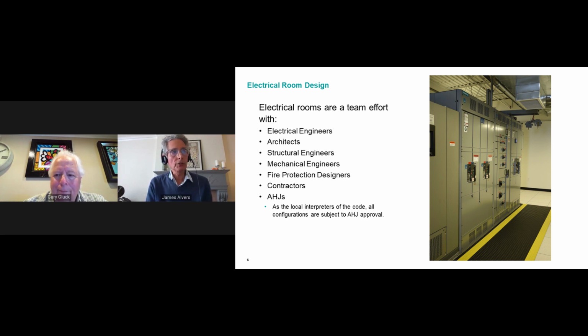The picture you see in the slide shows a switchboard, and we're going to be talking about switchboards, not switchgear. So typically you can place them against the wall. There are exceptions on occasion. You see in this case some individually mounted insulated case breakers, and another section with some molded case group mounted breakers. Both are okay for generator switchboards. Obviously, you're going to save space if you can use group mounted breakers in your design.